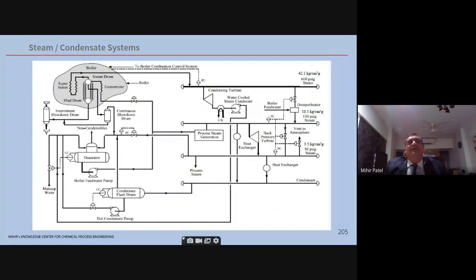Now a refinery may have all these three types of levels. One is the high pressure level, 42 kg. Second is medium pressure, which is 10 kg. Third is the low pressure, which is 3.5 kg. So a refinery may have all three pressure levels. Other industries, it depends on the requirements. But this diagram gives you an overall concept. So the steam header is going in the high pressure steam. It goes to the main header. Pressure PC is controlling the steam boiler firing rate completely. This steam header can be taken through a condensing turbine, okay, and you can produce power, or you can take it to a PRDS assembly.